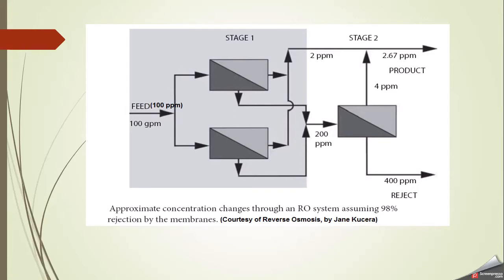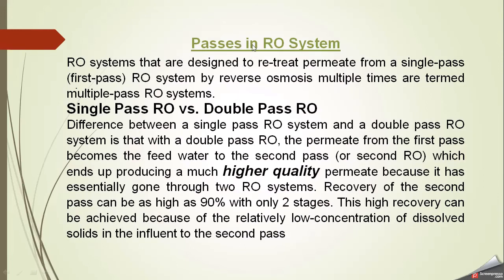Now we come to another important term: passes. People often confuse stages and passes. An RO system designed to retreat permeate from a single pass RO system by reverse osmosis multiple times is termed a multiple pass RO system. The key difference is this: in stages, the concentrate from the first stage enters the second stage, but in passes, the permeate from the first pass becomes the feed water of the second pass. In stages we feed concentrate forward; in passes we feed permeate forward.